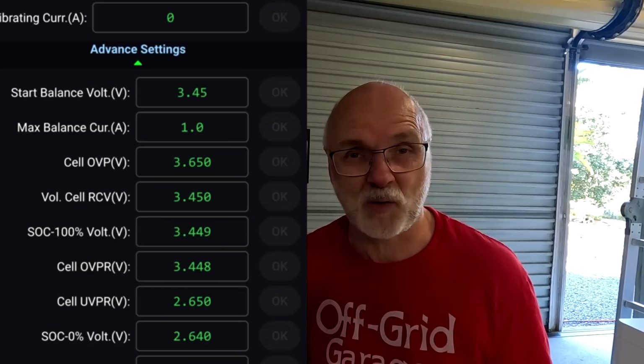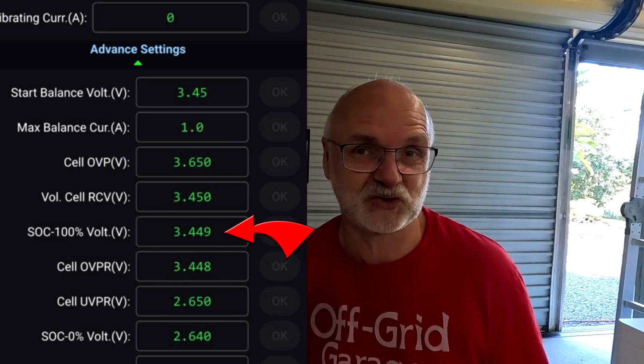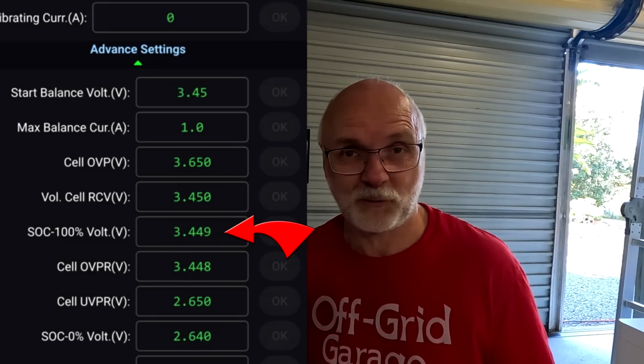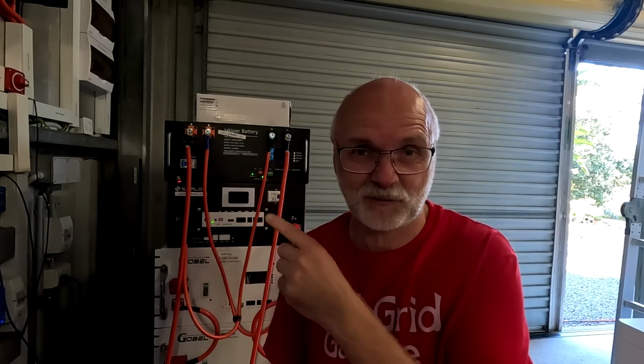This next one is the 100% state of charge trigger. As you know, the BMS has a voltage you can set, and when one of the cells of your whole battery reaches this voltage, it resets the BMS to 100%. This isn't quite correct, because we're not really at 100% if one cell reaches 3.5 volts, for example, but it's already better than what we had before. However, this exact feature causes issues with some inverters out there.